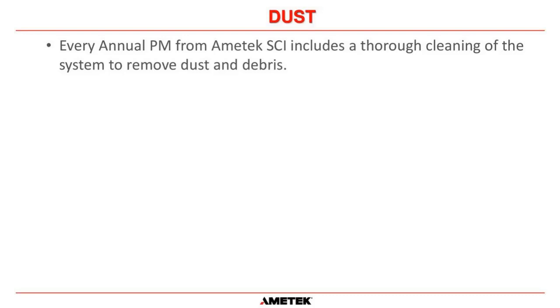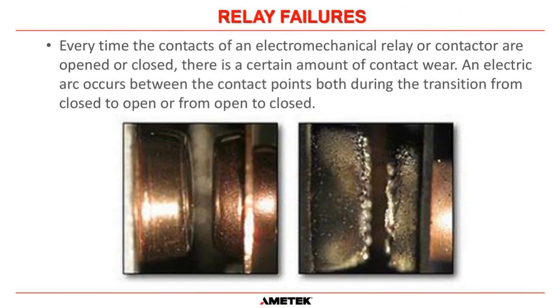So dust is actually very, very important to clean out. So another mode of failure is relays. Every time the contact of any switch, and obviously a relay is just an electromechanical switch, there is a certain amount of contact wear.